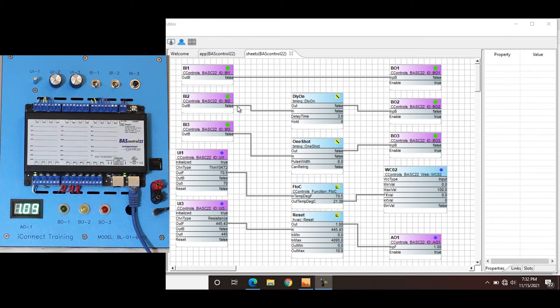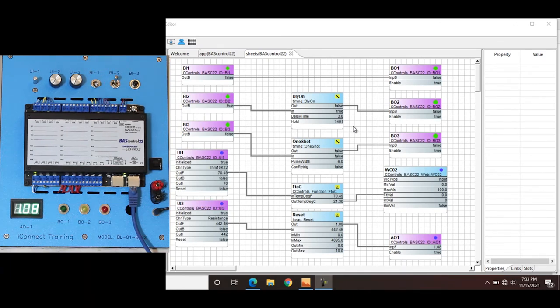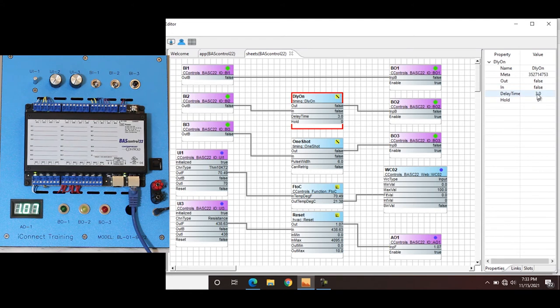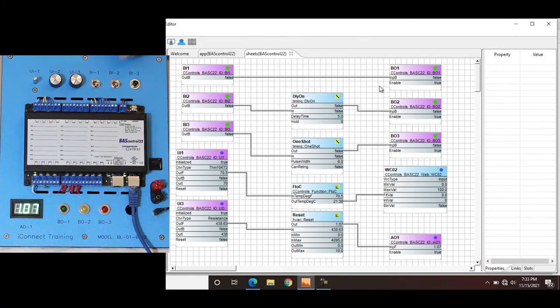Binary input 2 right now is false — it feeds into the delay on in. We've set a three-second delay time, so let's try it out: one, two, three, and it turned on — you can see the light. Now when we turn it off there's no delay time. To change the delay time we click the component, and in our properties pane we go to delay time and set it for five seconds or whatever it may be. Now when we click it on, you can see the hold countdown, and after five seconds it switches to true.